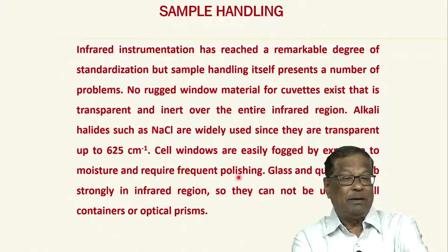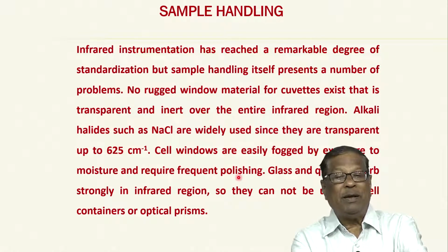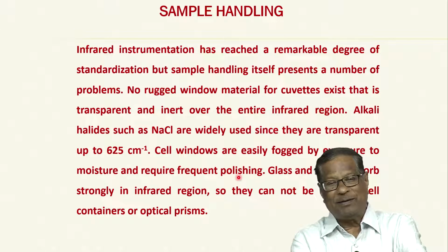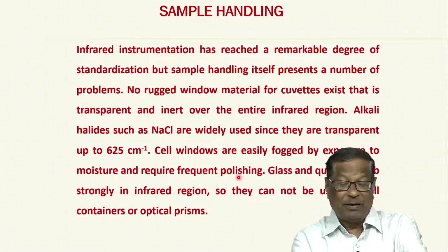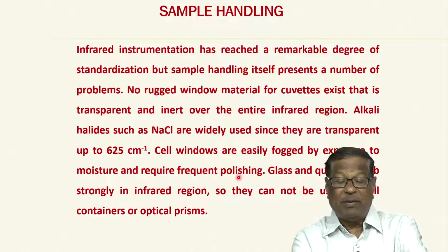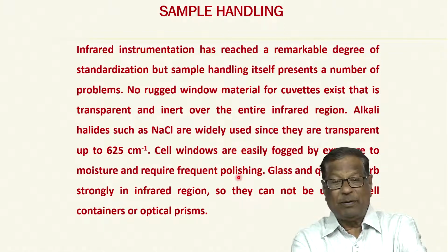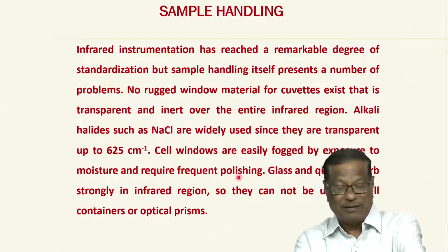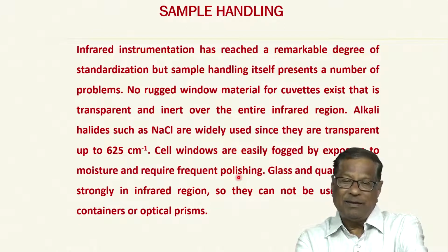But the problem is, whenever you use sodium chloride, you cannot have moisture in the sample. You cannot take the IR spectrum of water, is it not? Because water will dissolve the cuvette. So the cuvettes will get deformed and then there will be a lot of errors and the spectrum will not be pure at all. Cell windows especially get fogged by exposure to moisture, because they are all made of sodium chloride crystals. So fogging is a great problem.